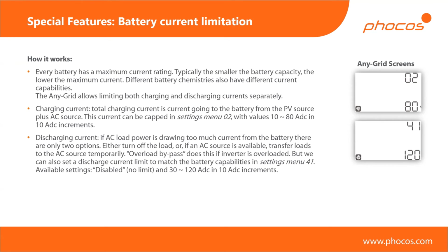And then automatically, as soon as it detects that your battery is being discharged with more than 40 amps, it will temporarily switch over to the grid. Obviously, if the grid is available. If it's not available, the only thing you can do is shut down. What's important to know here as well is that, depending on how you size your system, this shouldn't happen if you size your system well.